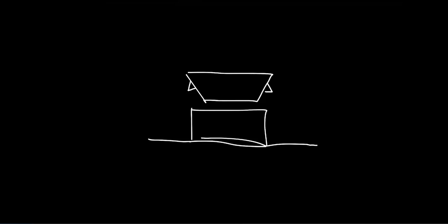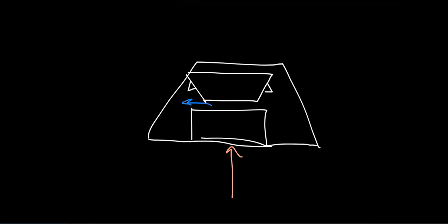The basic parts of a chilled beam are a primary air plenum, nozzles which are stamped into the primary air plenum, a heat exchange coil, supply air slots, the induction grill, and finally, a case to hold it all together. An active beam works by ducting primary air from a central air handler to the beam's air connection. Nozzles stamped into the plenum create small jets of air just above the coil. This induces room air through the coil where it can be cooled or heated.